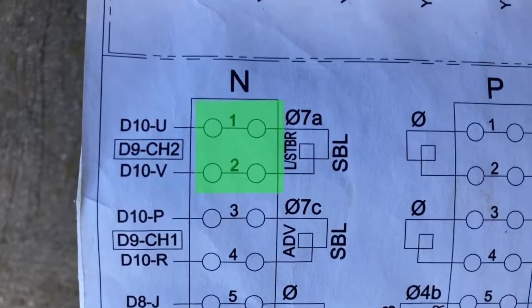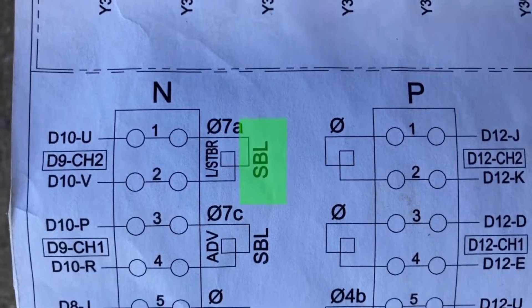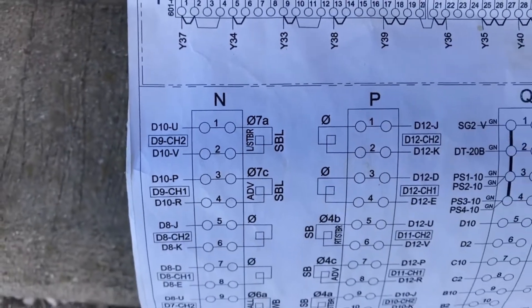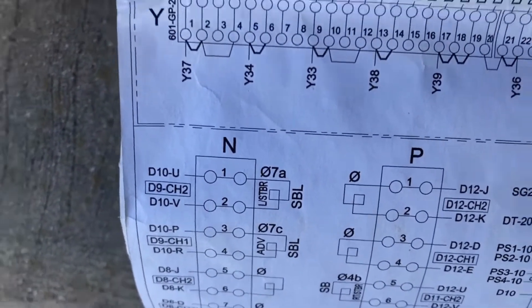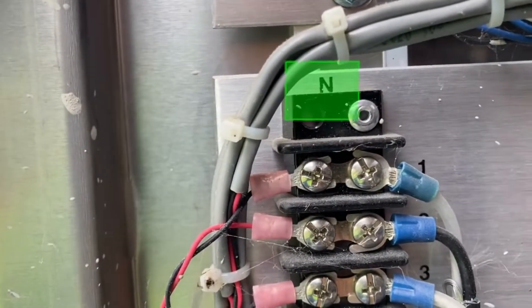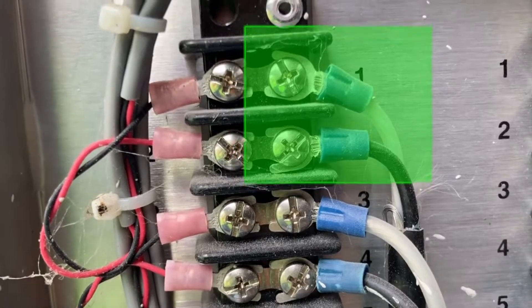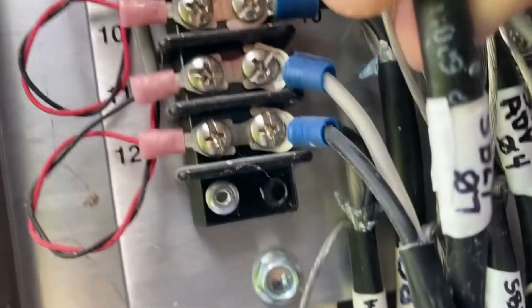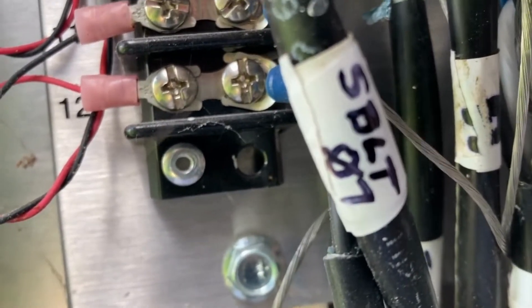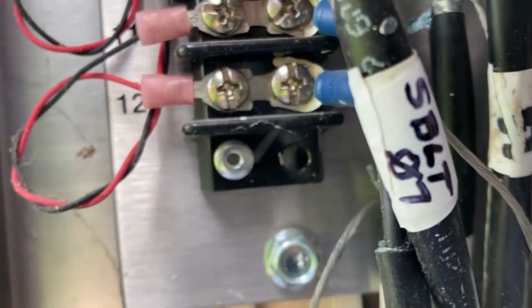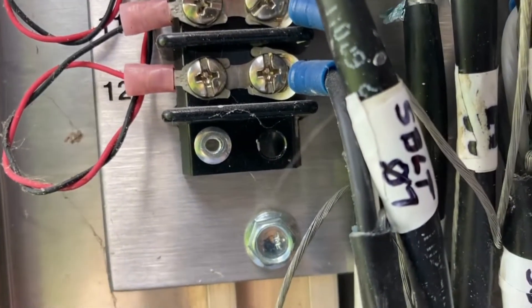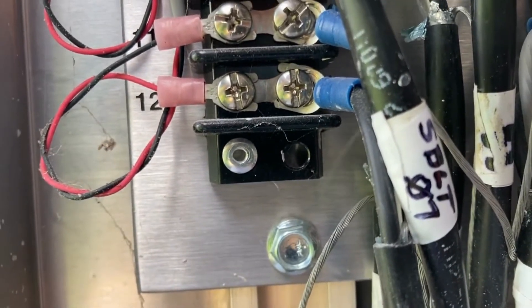For instance, for N1 and N2 right there, we've got phase 7 southbound left turn. I've already taken the step to get that loop labeled. If you follow N1 and N2, you've got to find the N terminal — there's the N terminal over here. Find the loop that's on there: 1 and 2. Right there — I started labeling it, and there it is: southbound left turn, phase 7. I put the direction and the phase, and now for future reference I always know that that direction and phase is for that loop.